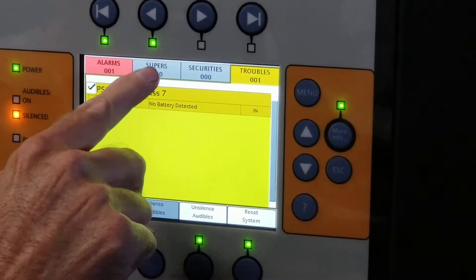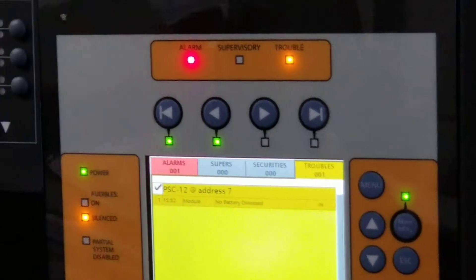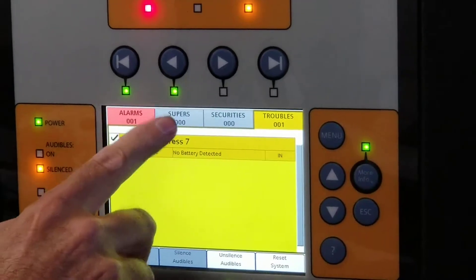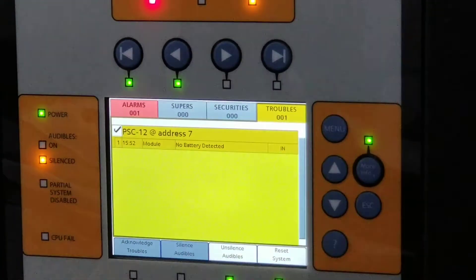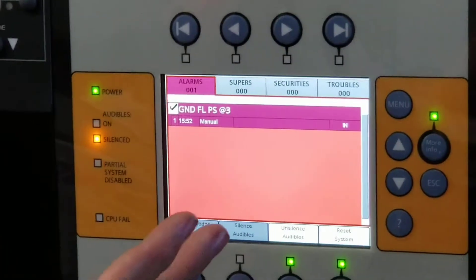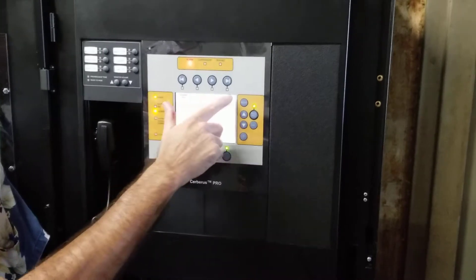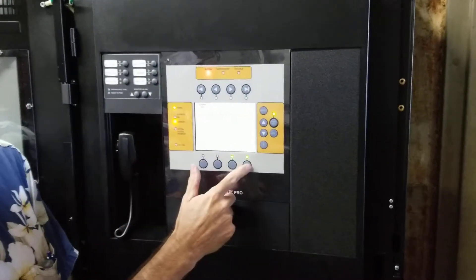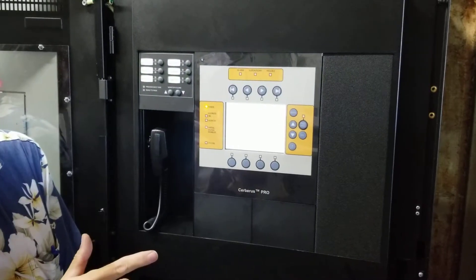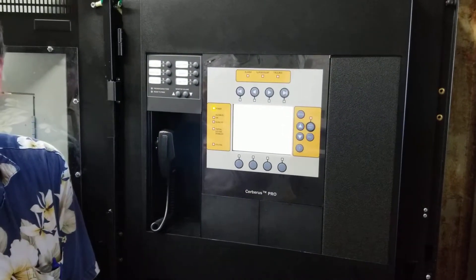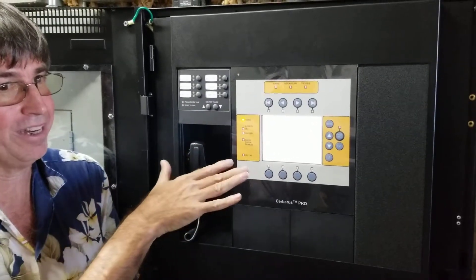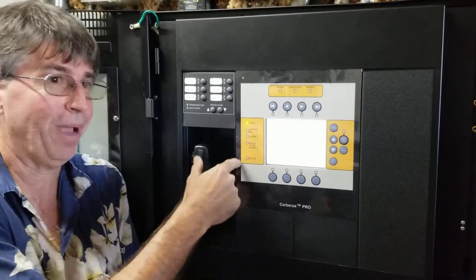This is all your classification. You could have a supervisory — an example of a supervisory is a tamper valve in the sprinkler system if somebody closes that, that would be a supervisory. Trouble is any trouble in the system. An alarm. Security is a security alarm if you're integrated into the security system, which there is not. For the reset system, you always want to check these four tabs up here.